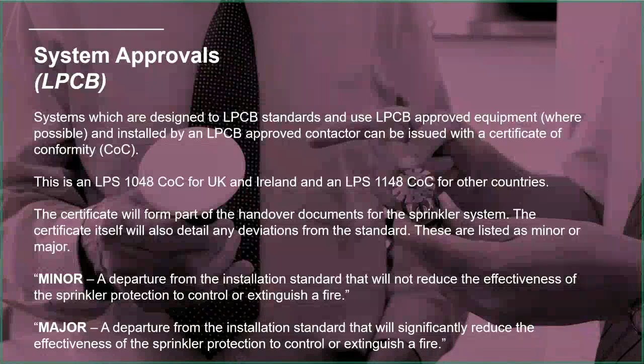A major non-conformance is a departure from the installation standard that would significantly reduce the effectiveness of the sprinkler protection to control or extinguish a fire. A silly example would be if there's no stored water - you've got a pump, pipes, heads, but no stored water. That would be a major non-conformance, and the certificate would not be issued under those circumstances.